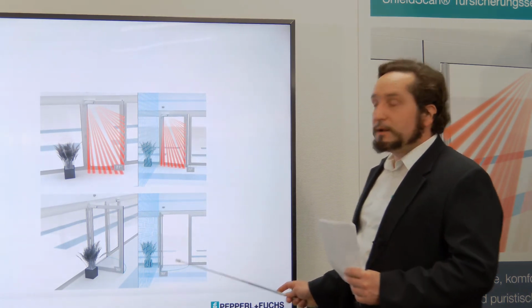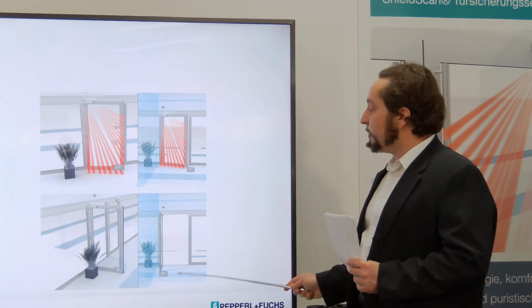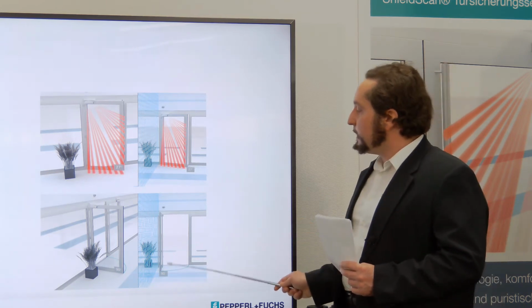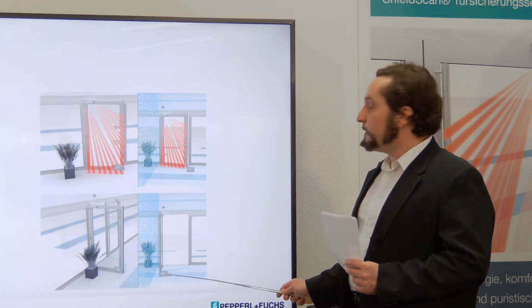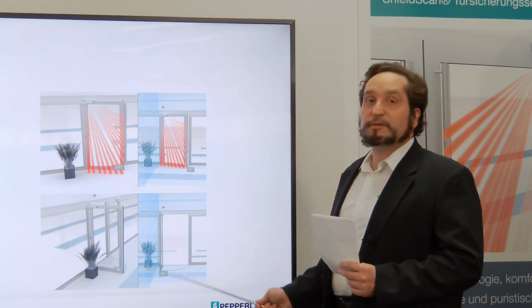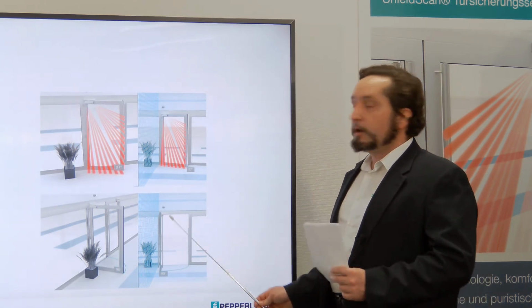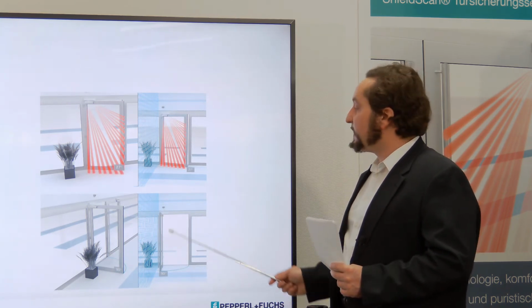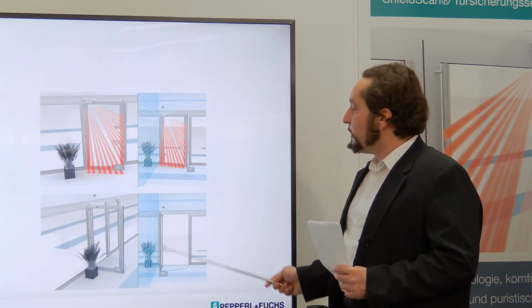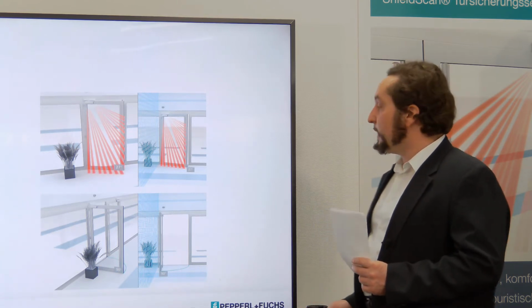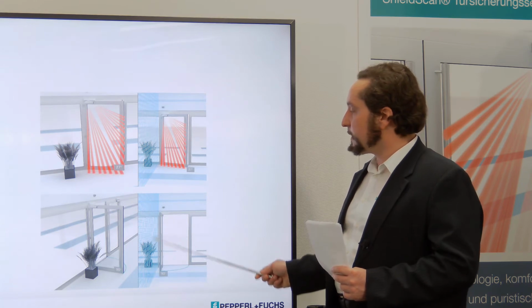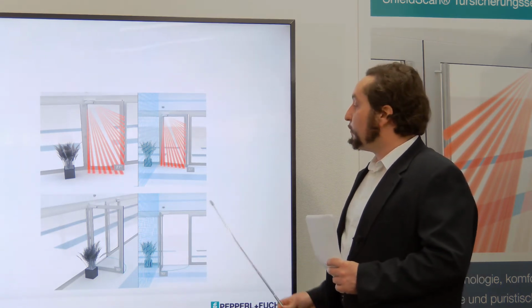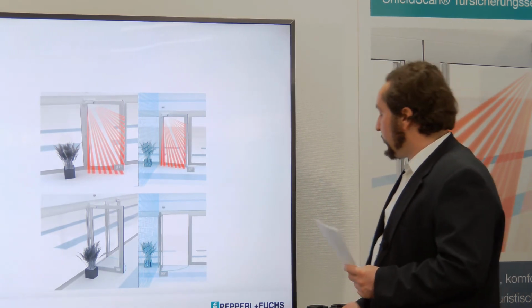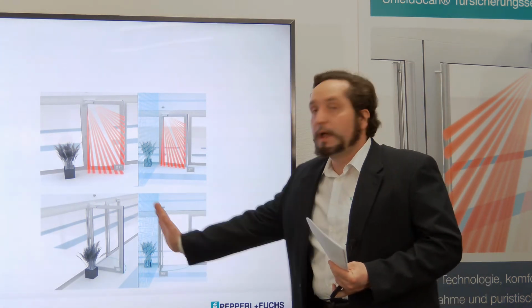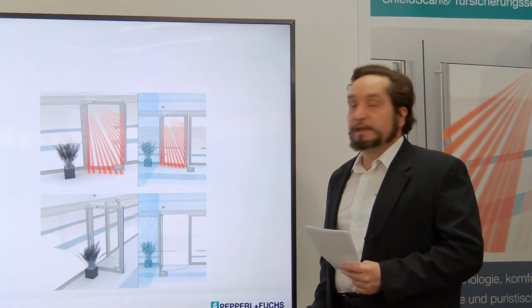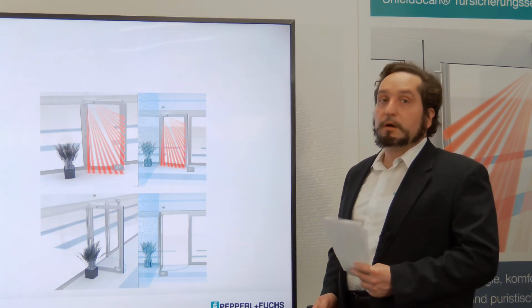The final result of this effect we see in the picture underneath the first one. Here the door now has completely opened, angle now 90 degrees. All of the single light beams have now reached the virtual wall, and they are all hidden, all suppressed, so they are no longer shown in this picture. They are still operating, still switched on, but their detection is no longer evaluated by the sensor. So if they hit or detect objects behind the virtual wall, they will not be evaluated or detected. We have uncoupled this complete zone behind the open door, and changes there will not influence the sensor operation.